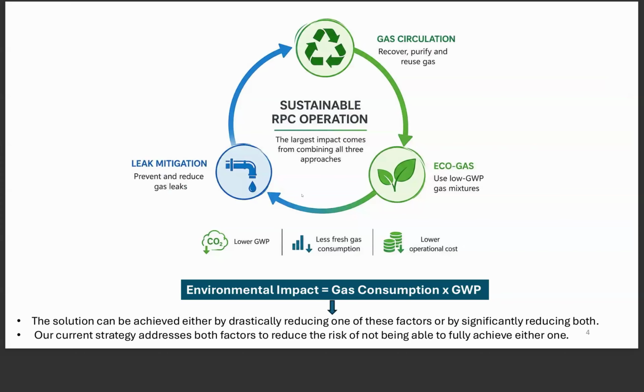The environmental impact depends on two factors: if we combine leak mitigation and gas circulation, the first is gas consumption, and the other is the global warming potential of the gas. If we reduce one of them significantly, we can gain a lot, but if we reduce both in parallel, the overall impact will be much larger. That's why our strategy is to work on both in parallel.